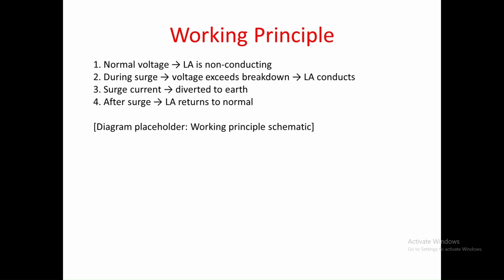So the basic principle is for the lightning arrestor, it stays non-conducting during normal voltage, that is the standard operating voltage, may it be 33 kV, 132 kV, 220 or 400 kV, and during the surge the voltage that exceeds leads to the breakdown of the metal oxide varistors inside the LA, and it starts conducting, which leads to the diversion of the surge to earth, and again after the surge is over the LA returns to its normal position.